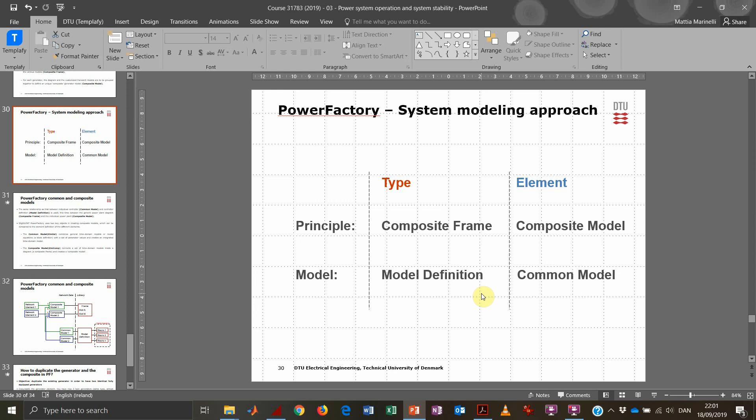The common model gives gain and values to a specific governor — it essentially gives the governor its name. So if we have two identical governors in two different power plants, we have two common models referring to the same model definition. Similarly, the composite frame is a block diagram setting the relationship between different model definitions, and the composite model points to a specific composite frame, gathering together all the dynamic models.